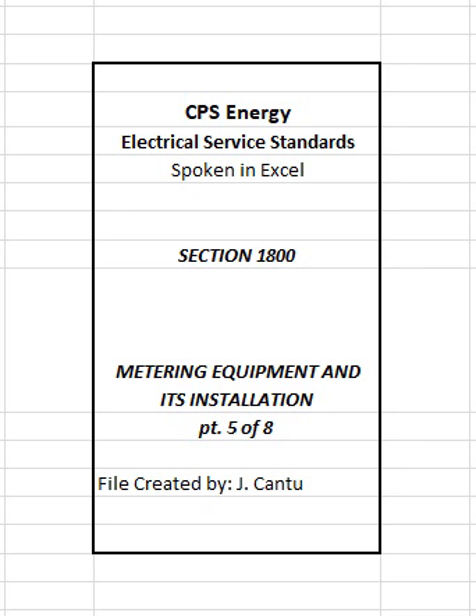1806. Heights of metering equipment. Single position, self-contained meter sockets and transformer-rated meter sockets including trans sockets must be mounted so that the center of the meters will be not less than 4 feet or more than 6 feet above final grade or floor level. Exception 1. Where single-position meter sockets are protected in meter rooms, basements, or approved decorative meter enclosures, the minimum height may be reduced to 3 feet if pre-approved by CPS Energy's customer service representative.